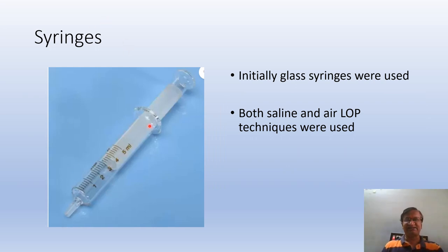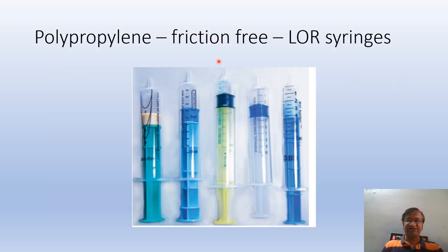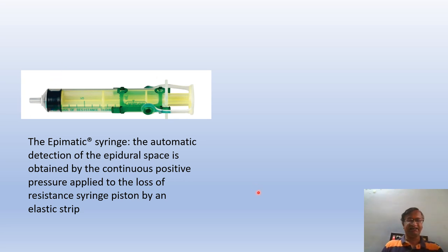Regarding epidural syringes: previously we used glass syringes, and both saline and air LOP (loss of pressure) techniques were used with glass syringes. These have gone out in favor of LOR syringes — polypropylene friction-free loss-of-resistance syringes. There are so many models and companies. The Epimatic syringe provides automatic detection of the epidural space: if you give continuous positive pressure, this elastic strip will release and automatically detect the epidural space.